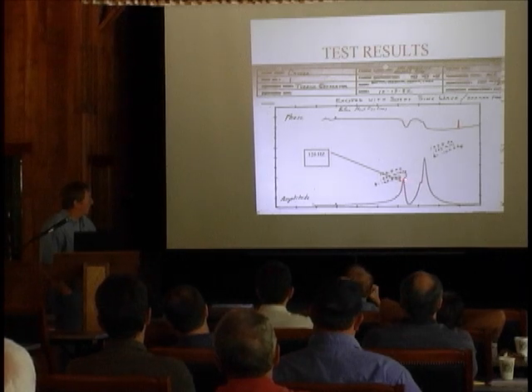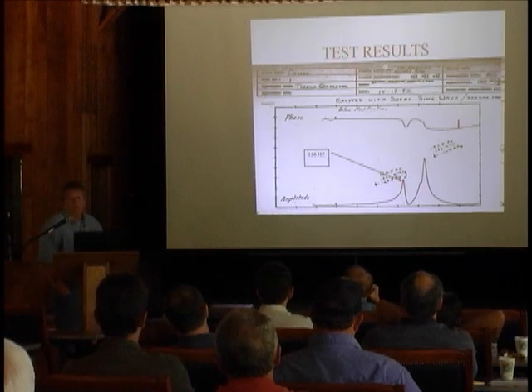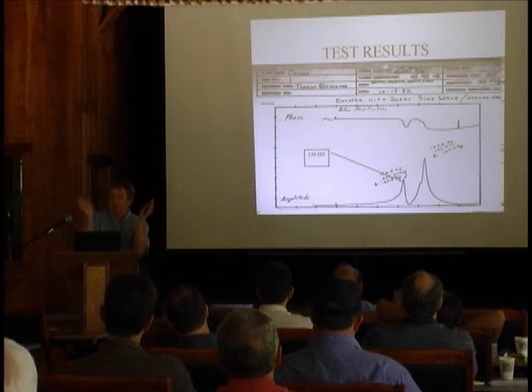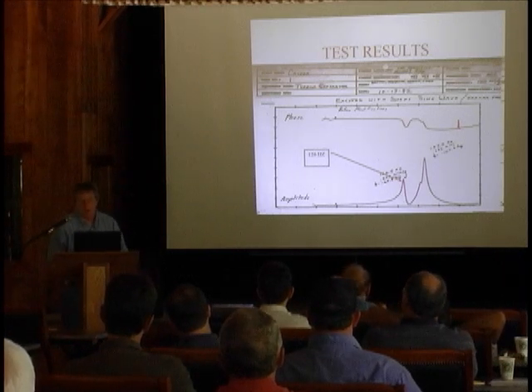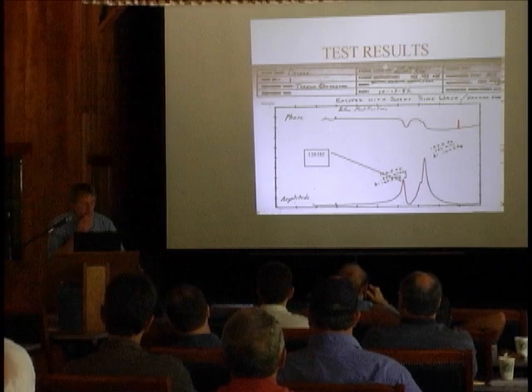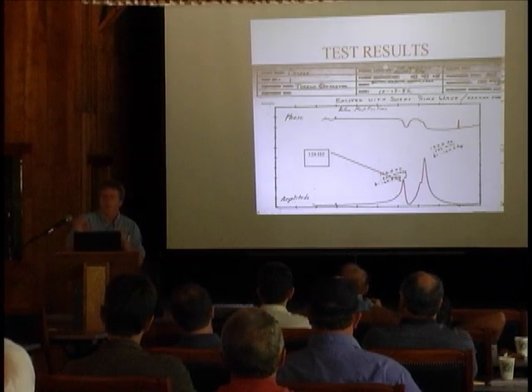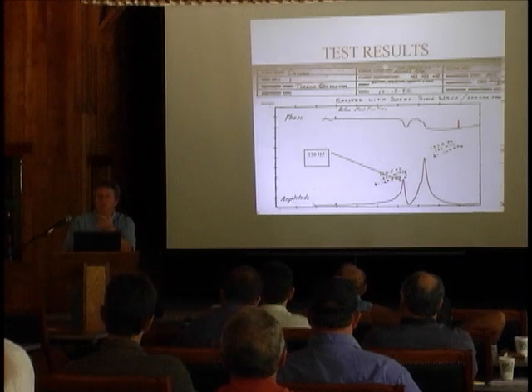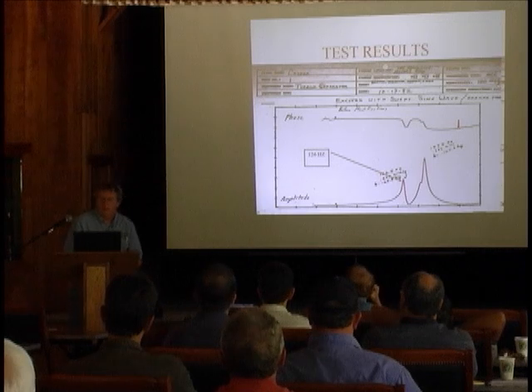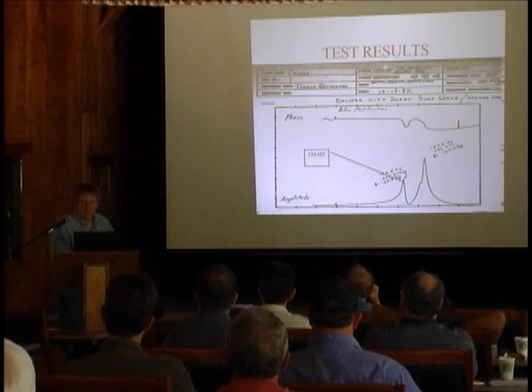That's cold. As you heat the unit up, this will actually drop, and that causes you to operate right on 120 hertz resonance. And then the phase leads actually sit there and they shake. And when you take the unit apart, you take the end bells off, you can actually take your finger and rub next to these, and the fiberglass would turn into like a talcum powder, yellow stuff. And I used to test these every single year.